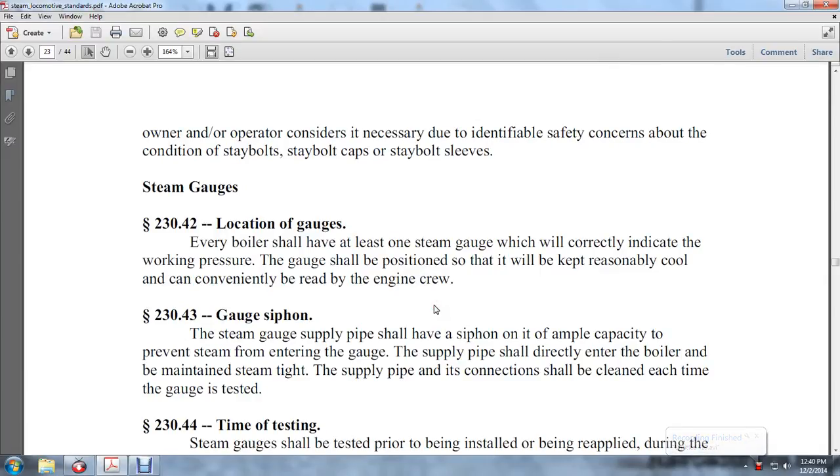Steam gauges, 230-42: Location of the gauge. Every boiler should have at least one steam gauge which correctly indicates the working pressure. The gauge shall be positioned so that it will conveniently be read by the engine crew.